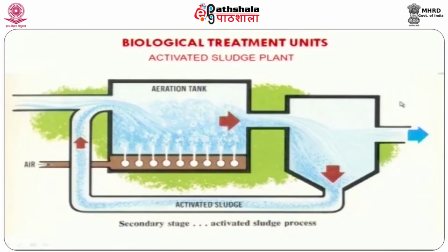Here in the activated sludge scheme, the secondary settler will act as a solid liquid separator. With the aid of gravity pull, we are trying to remove biological mass that will be generated during aerobic transformation. So, 30 to 40% of the active microbial population is sent back to the reactor again. To maintain MLSS population in the range of 2000 to 3000 milligram per liter, solids retention time for the conventional carbon oxidation process may be in the range of 8 to 10 days. If you want to achieve nitrification, we have to enhance solids retention time up to a maximum level of 15 days. In this way, these two different bacteria, carbon oxidizing bacteria as well as slow growing nitrifying bacteria, may be there in our biological system.